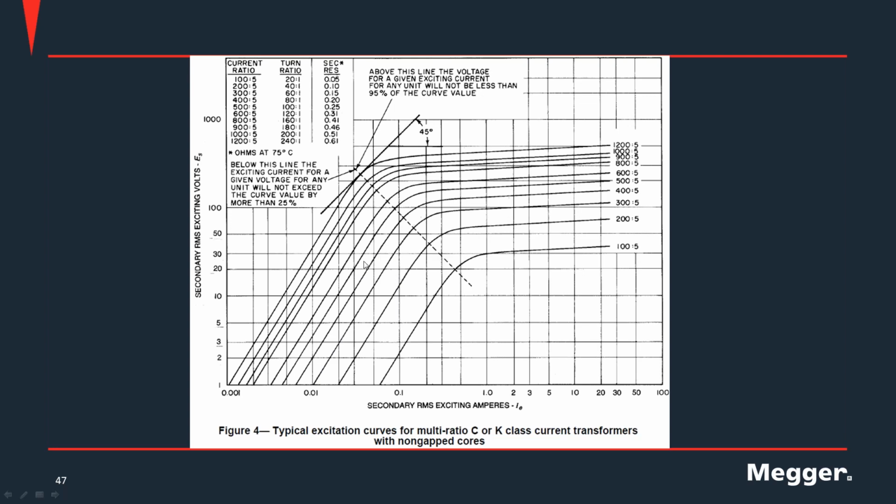So in here, you will see that when I have this excitation voltage, again, this excitation voltage is caused by the primary current. As you have seen in my diagram before, as you increase the primary current, you increase the voltage across the secondary winding. When you increase the voltage across the secondary winding, then you will have excitation current. And what does the excitation current mean? As I've said a while ago, these are errors.